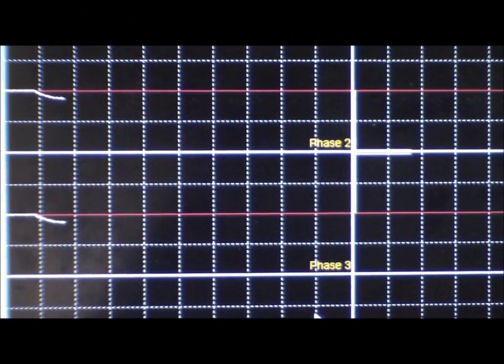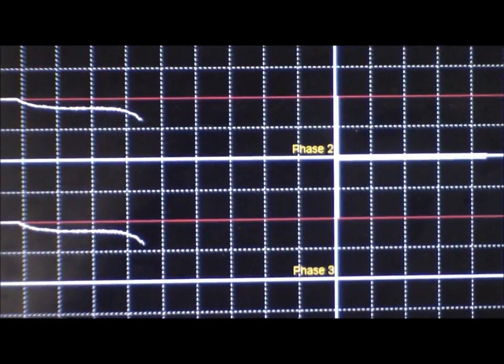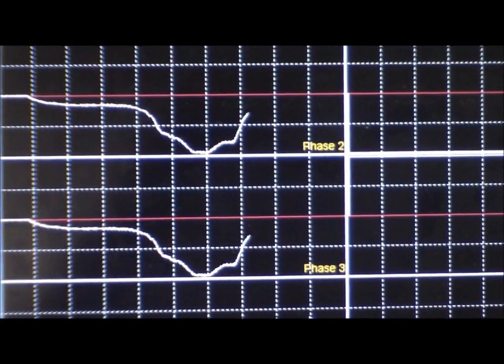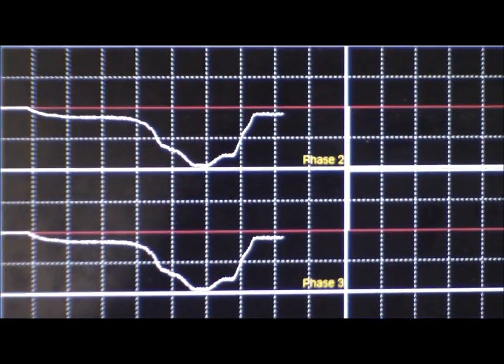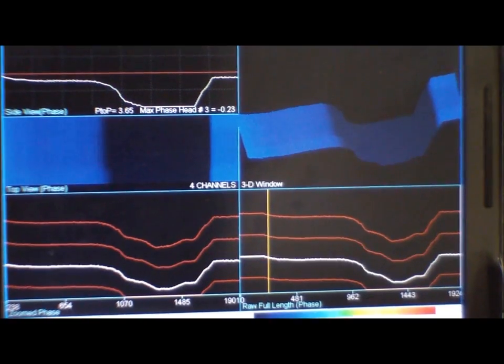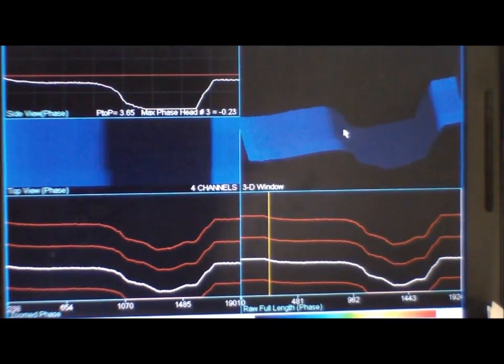This is a calibration pull on a 50% magnetite blockage calibration. You can see the drop in the signal. And the next screen is the processed version. You can see the individual channels and a 3D image, which of course we can manipulate.